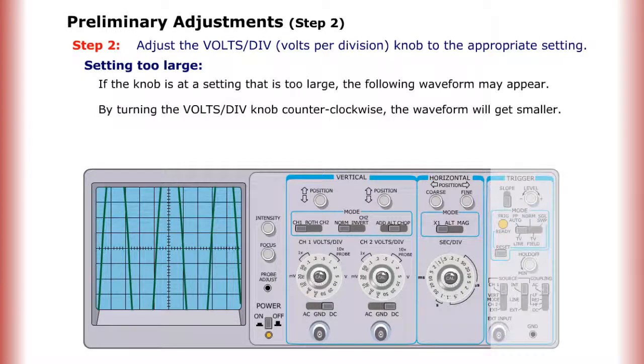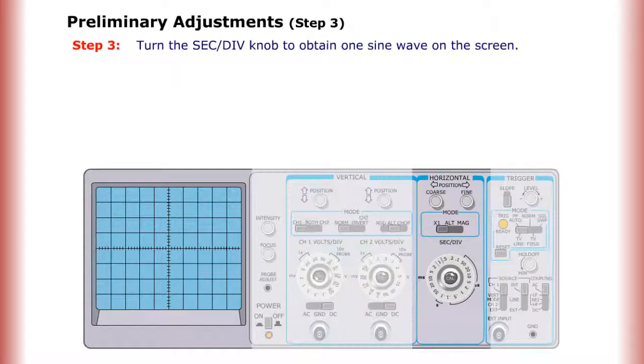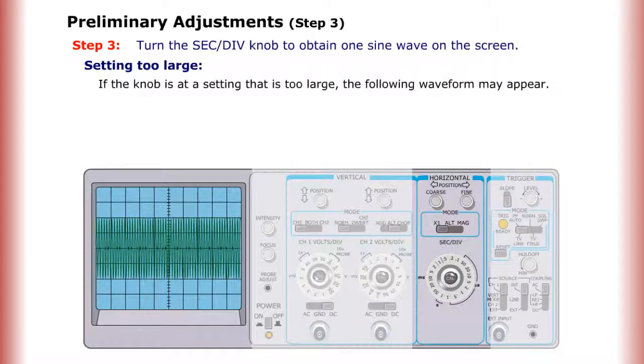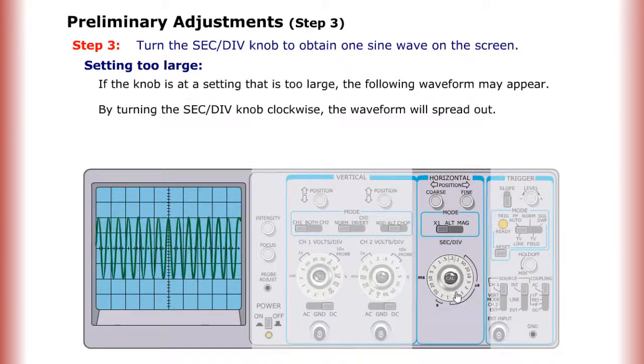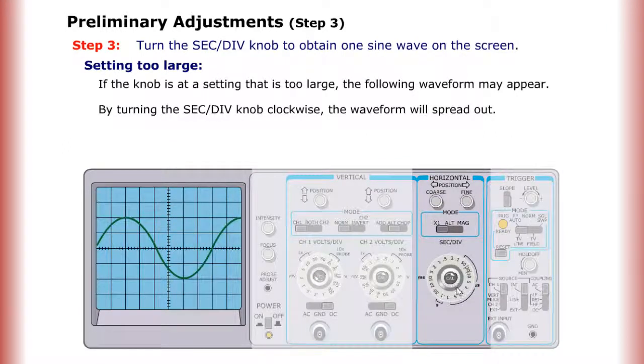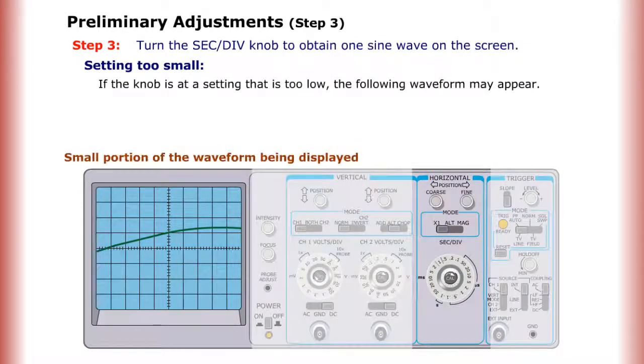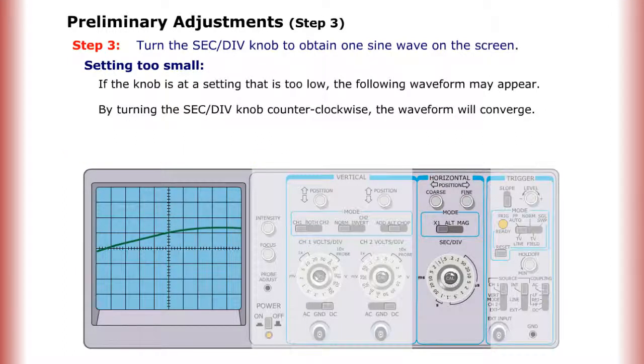By turning the volts per division knob counterclockwise, the waveform will get smaller. Turn the seconds per division knob to obtain one sine wave on the screen. If the knob is set too large, too many waves are displayed; turning the seconds per division knob clockwise will spread the waveform out. If the knob is set too small, only a small portion of the waveform is displayed; turning the seconds per division knob counterclockwise will cause the waveform to converge.